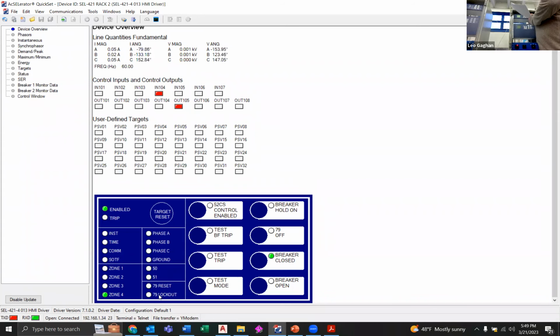Okay. So another one that we'll try is we'll try reclosing with reclosing off. Let's see. Yeah, hopefully it shouldn't reclose. I gotta wait for that LED to set itself. It's a setting called a reclaim time. I think you guys recently saw something called switch onto fault.